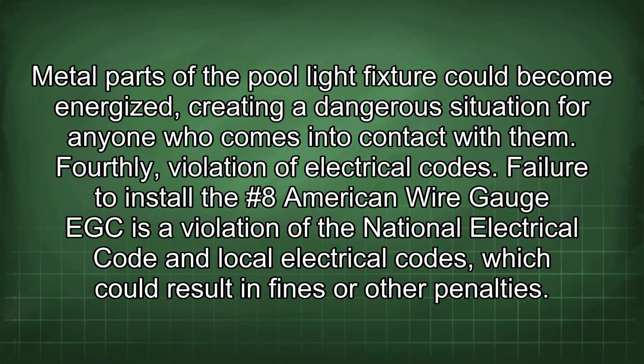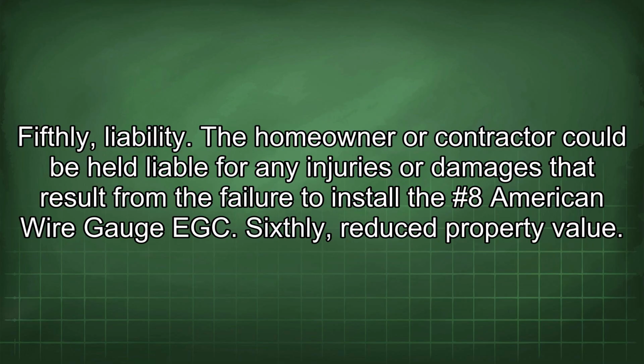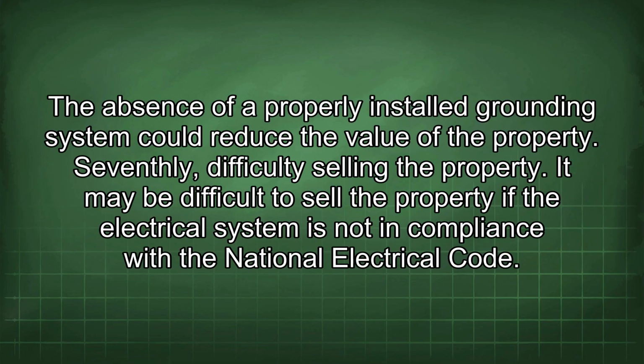Fourthly, violation of electrical codes. Failure to install the #8 American wire gauge EGC is a violation of the National Electrical Code and local electrical codes, which could result in fines or other penalties. Fifthly, liability. The homeowner or contractor could be held liable for any injuries or damages that result from the failure to install the #8 American wire gauge EGC. Sixthly, reduced property value. The absence of a properly installed grounding system could reduce the value of the property. Seventhly, difficulty selling the property. It may be difficult to sell the property if the electrical system is not in compliance with the National Electrical Code.